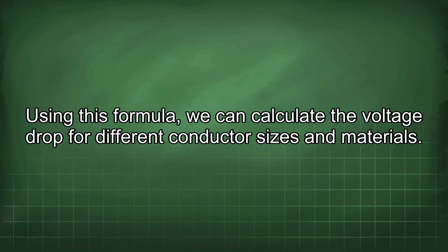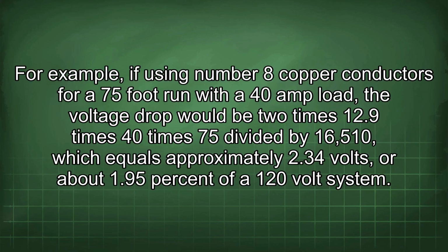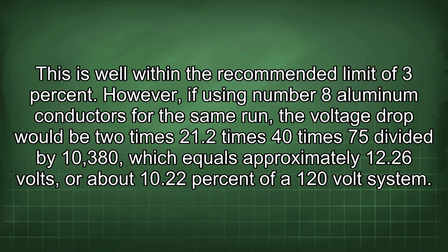Using this formula, we can calculate the voltage drop for different conductor sizes and materials. For example, if using number 8 copper conductors for a 75-foot run with a 40 amp load, the voltage drop would be 2 times 12.9 times 40 times 75 divided by 16,510, which equals approximately 2.34 volts, or about 1.95% of a 120 volt system. This is well within the recommended limit of 3%.